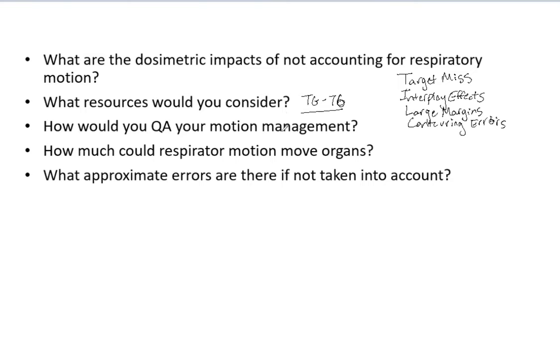How would you QA your motion management? Varian has an infrared box — essentially a respiratory motion phantom. There's also a Quasar phantom that moves a target. You want to test that the tracking is accurate and that it beams off when out of tolerance. You at least need to do an annual end-to-end test from CT to treatment, and for that you want to follow TG-142. TG-76 also discusses it. Don't go too far into the weeds — just mention what you know.